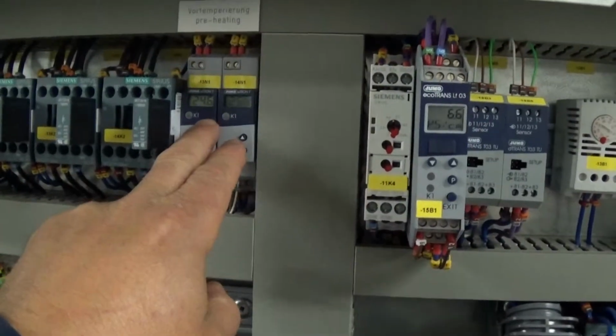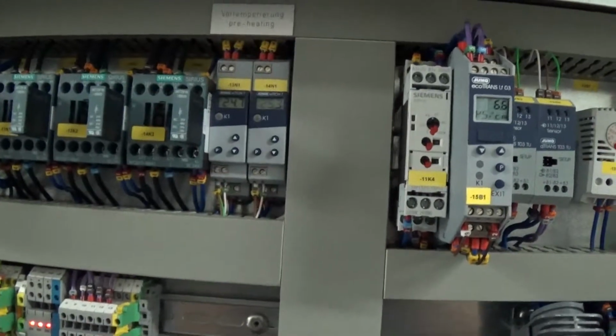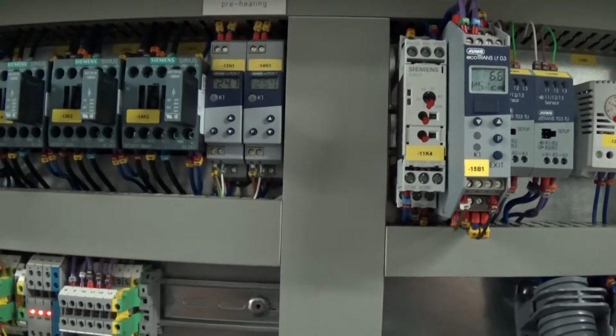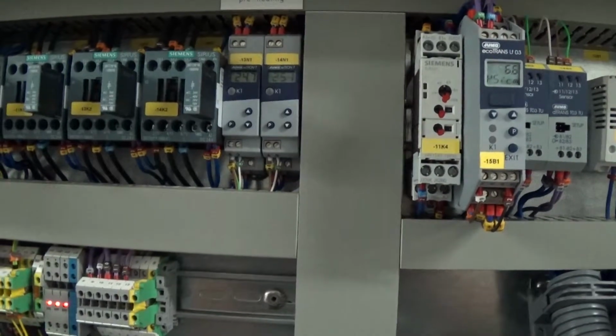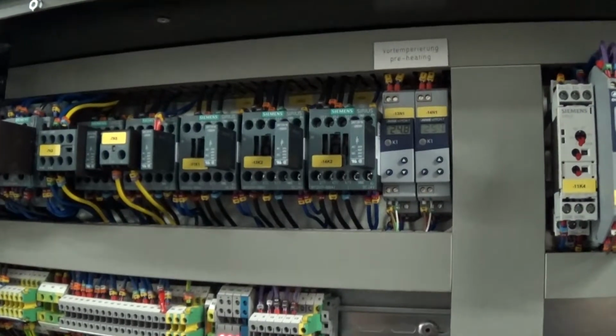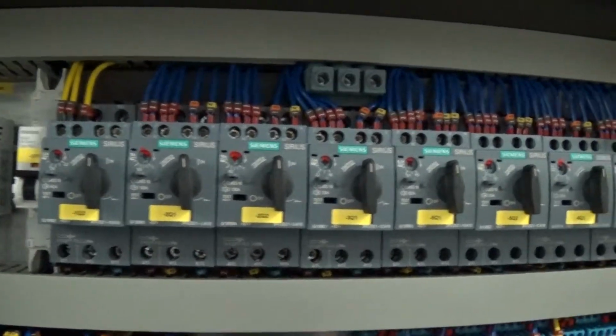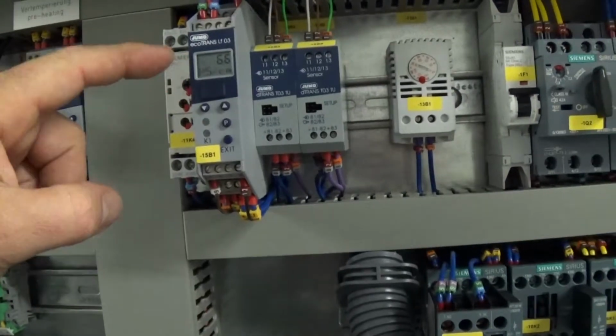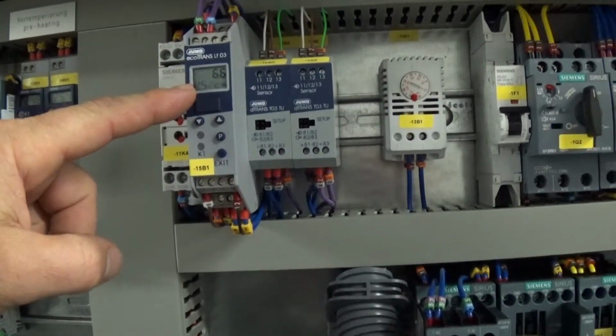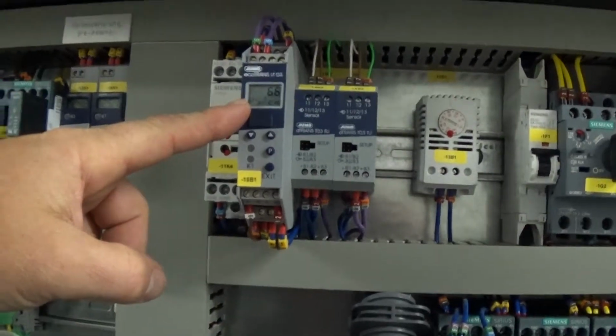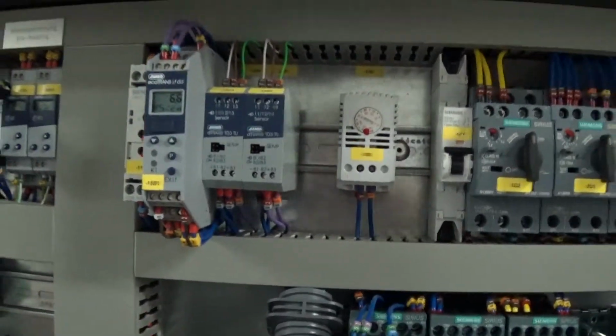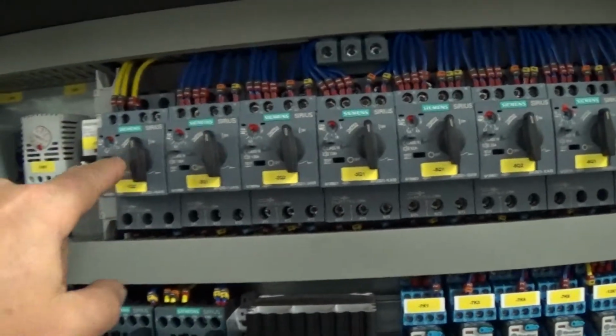These here are your 2 little temperature controllers for the heaters that are in the tank, and we'll set those to a low position, so those will not be relevant. Then we have a series of our contactors here for fans and compressors, and we have our overloads here. The unit also has DI resistivity sensing. Well, that's not going to affect in any way your basic cooling for your basic application. So again, these are all our contactors and our overloads.